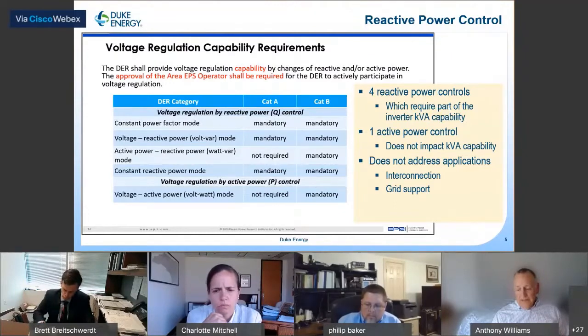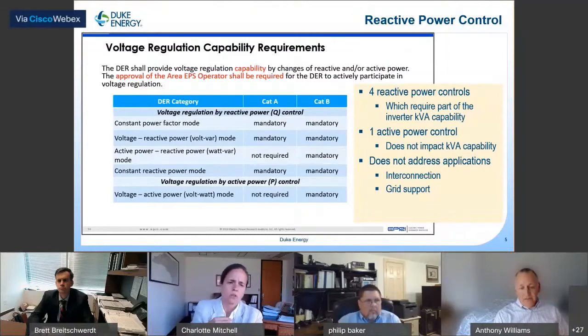Many times, because the DER, the inverter, is injecting active power that causes voltage to rise, that can create a voltage violation. So if they absorb reactive power, that brings the voltage down, which may remove the violation, so they don't have a violation for interconnection. That's how we're using it in terms of interconnection, but not so much as 'hey, we just want to maintain 124 volts on the system, so you regulate the voltage.' That would be more grid support, and we're not looking at that piece right now.